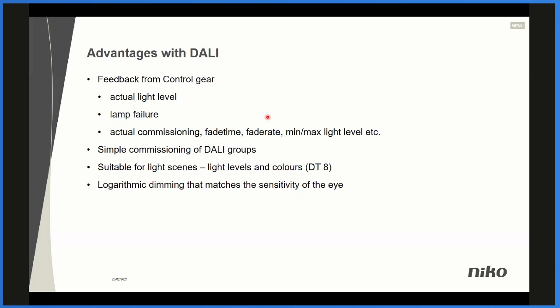We can read out the actual commissioning. That means the fade time, fade rate. I'll explain that a little later. The minimum and maximum levels, and so on. And this is simple commissioning of the DALI groups that we have, and it's very suitable for light scenes. You can have different light levels, and as the previous presenters said, there are the colors, it could be tunable light, or as you said, human-centric lighting, and that means we have to have special device type 8. That means this is the device type that can change color.